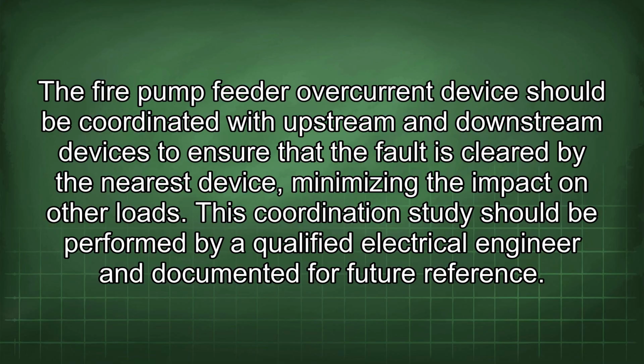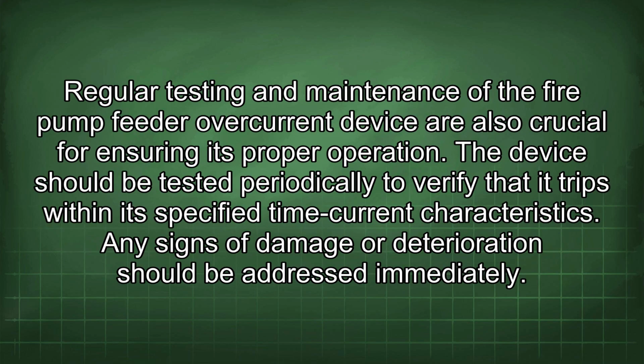This coordination study should be performed by a qualified electrical engineer and documented for future reference. Regular testing and maintenance of the fire pump feeder overcurrent device are also crucial for ensuring its proper operation. The device should be tested periodically to verify that it trips within its specified time current characteristics. Any signs of damage or deterioration should be addressed immediately.